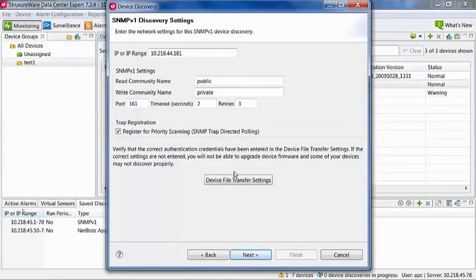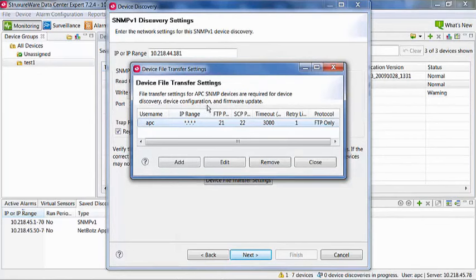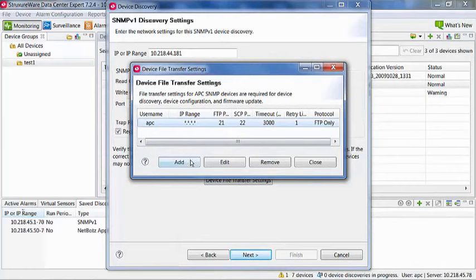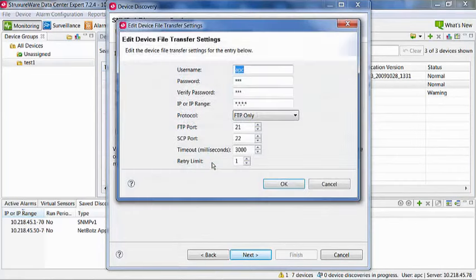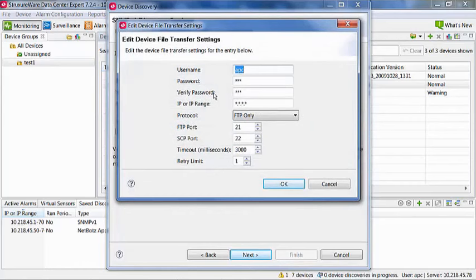Device file transfer settings is another option for APC devices only. During device discovery, we download specific files from the APC device for configuration and to define the specific alerts for the device being added. You can edit the defaults or create new entries. You can also add entries for specific device IPs or for ranges.